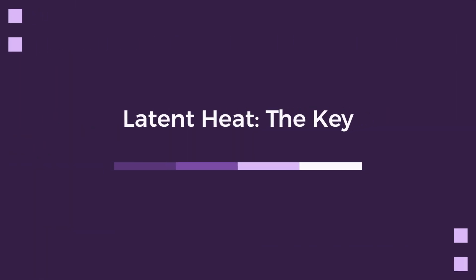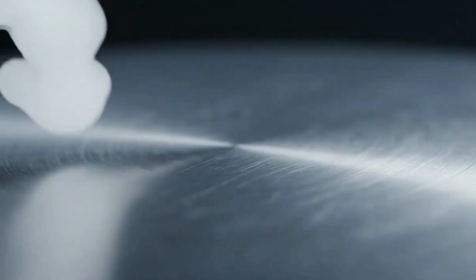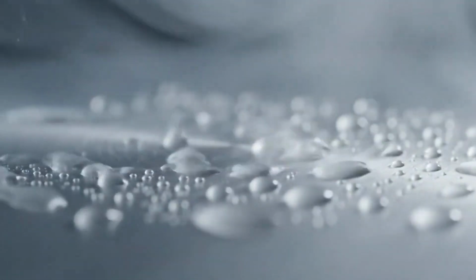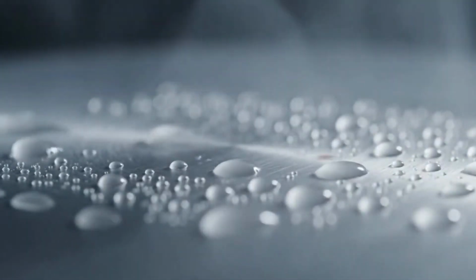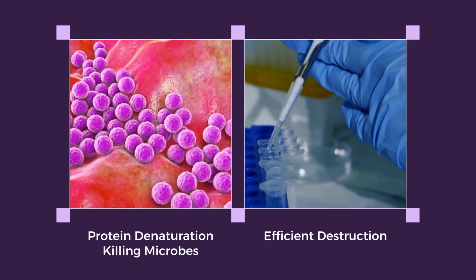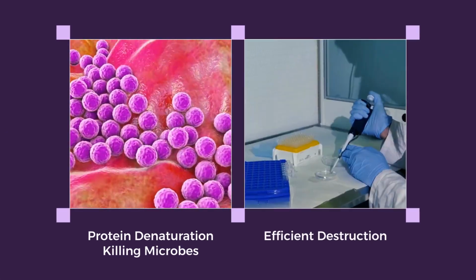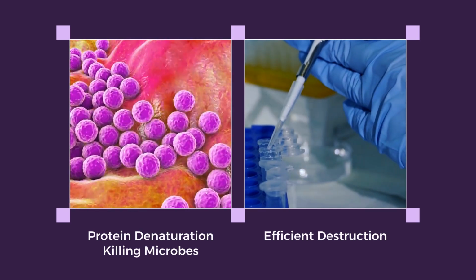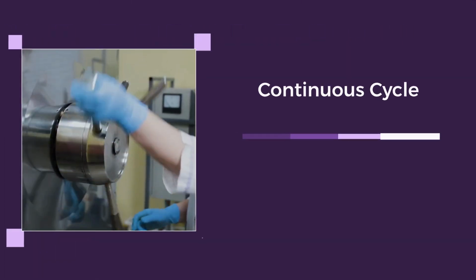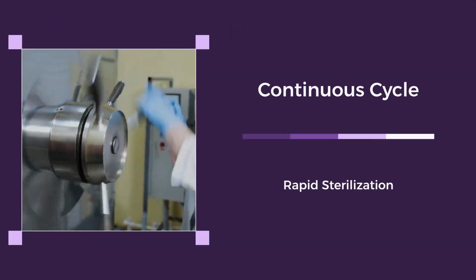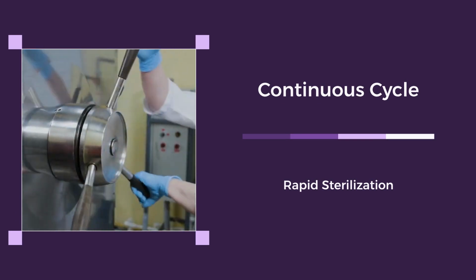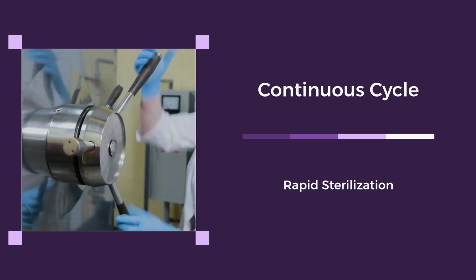Why is this steam so effective? It all comes down to latent heat. When this perfectly balanced steam hits a cooler surface, it instantly condenses from a gas to a liquid, releasing a massive amount of energy. This rapid energy transfer is what destroys the essential proteins of microorganisms, killing them with incredible efficiency. This continuous cycle ensures sustained, effective heat transfer, making dry saturated steam the most efficient choice for sterilization.